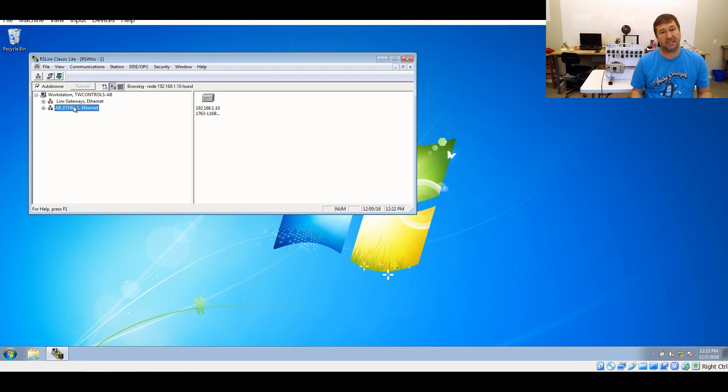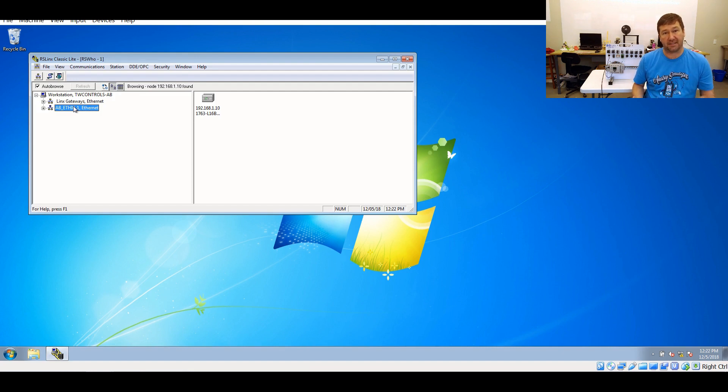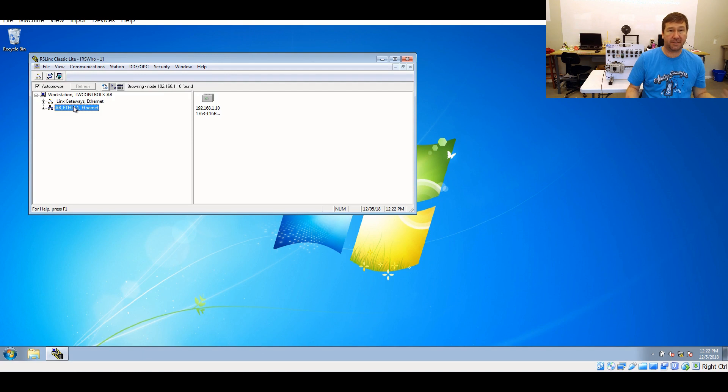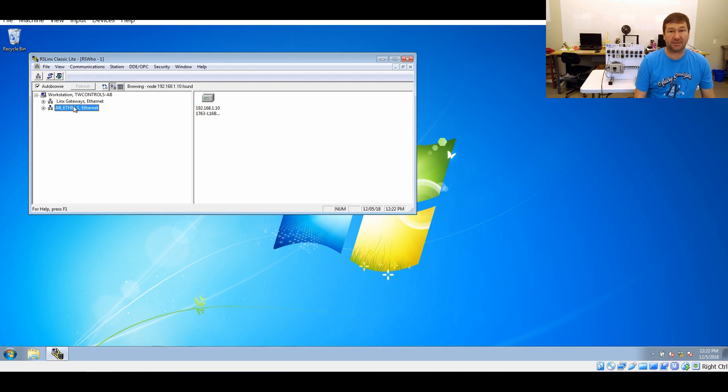Let's say that it didn't show up. There's two possibilities. One, something is blocking the broadcast packets that the Ethernet IP driver uses. Or there's an issue with your network configuration. Next, we're going to try the Ethernet devices driver, just as if it didn't show up.